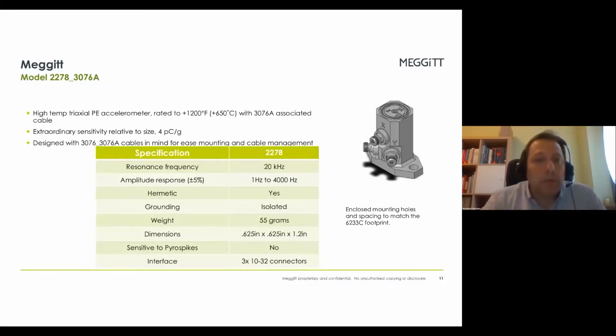Next one is the 2278, associated now with the 3076A cable. We will have a look afterwards at this cable. This is a triaxial unit that was introduced last year. It features very good nominal sensitivity of 4 picocoulomb per G for each of the channels. In fact, it's a triaxial unit, but basically it is 3 different sensors in a matrix. It can work constantly at 650 Celsius. This is the main advantage. It also features the same footprint as our bestseller 6233C unit for bolt mount. That's quite extraordinary for the size, and the weight is only 55 grams.